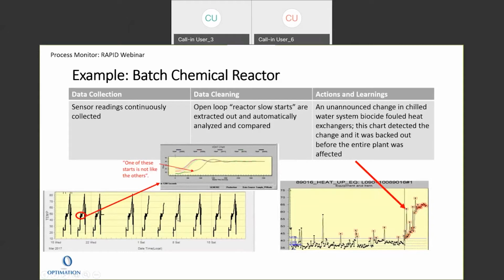It's kind of hard to tell what's going on different. But what we've done here is grabbed a small section of each of these and created a statistic for that section. In this case, it's the heat up of the chemicals to get to the set point. There's an initial temperature. In this case, this is blown up a little differently. Like 35 degrees here. This is actually the time it takes to go from the heat up, from the beginning to the end of the heat up time.